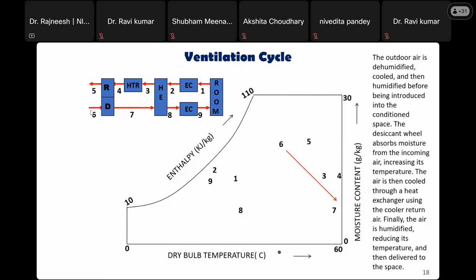So that is the latent load that is required to be taken up by the air conditioning system. Now this dehumidifier will take up the latent load. The air coming out of this dehumidifier will be a little bit heated, but the moisture content will be taken. Now you can understand the moisture content goes up in this direction, temperature goes up in this direction. So temperature is increased, but the moisture content is totally decreased.